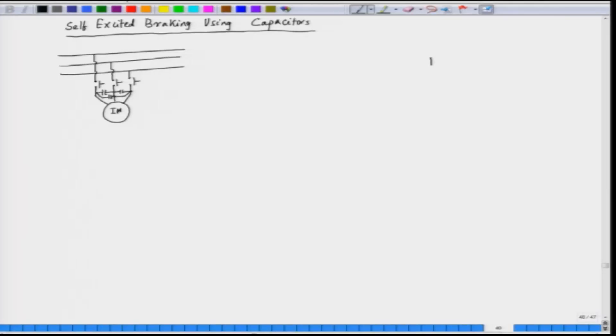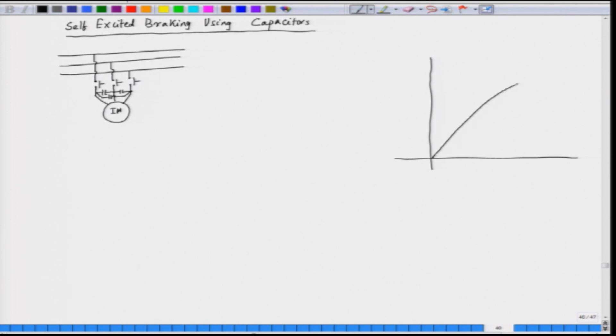The capacitor provides the necessary excitation to the motor. So the motor will have some excited voltage and that is called self-excitation, and the excitation is something very similar to that of the excitation of an induction generator. Let us see how it is excited. We have the magnetization characteristic here, and always we have some residual magnetism. This is the saturation characteristic because the core is a saturable core, and this is E, the phase voltage, plotted against I_m or I_c, the capacitor current RMS value.